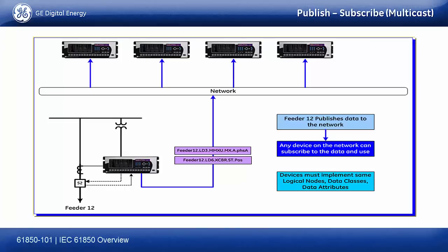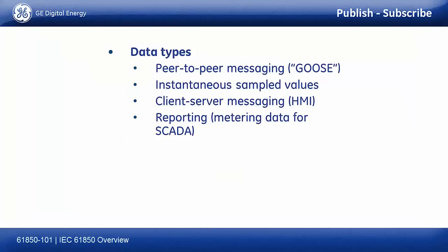It's kind of like me talking here, right? I'm talking out, and if you're paying attention and understanding what I'm saying, or even trying to understand, then you're subscribing to the data I'm publishing. If you're checking email or whatever, then you're not subscribing. It's the exact same model. The only requirement, of course, is that devices that subscribe have to implement the same logical nodes, data classes, and data attributes to understand what the data really is. But it's very simple. I'm going to push this out to the network and anybody can use it. I'm not sending it to a specific other device. I'm putting it on the network, and you configure the other device to say, if I want that data, I know how to get it.